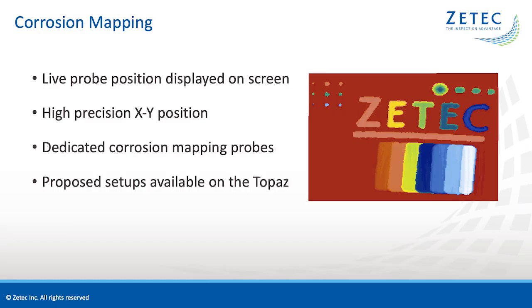The first user case we are going to look at is corrosion mapping. When using the Sweeper for corrosion mapping, you get live probe position displayed on the screen. Coupled with the high-precision X-Y position tracking, this allows you to look at the C-scan while it fills up so you are certain that every area is covered. Zetec's dedicated corrosion mapping probes are compatible with the Sweeper probe holder, so near-surface resolution is not a problem. Another advantage is that the UltraVision Touch software has proposed setups for corrosion.